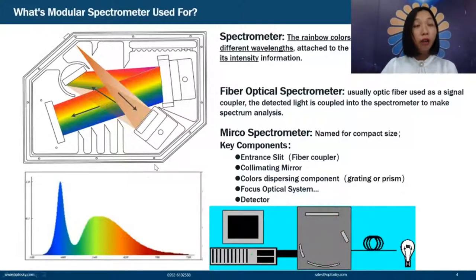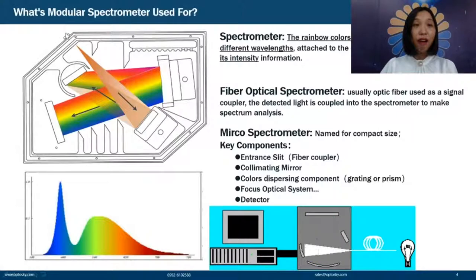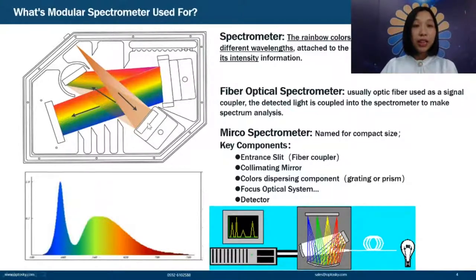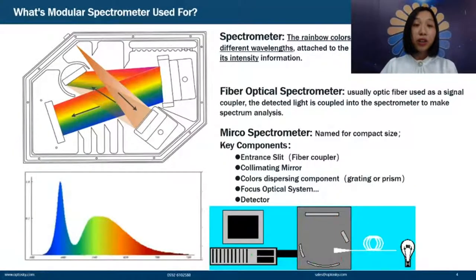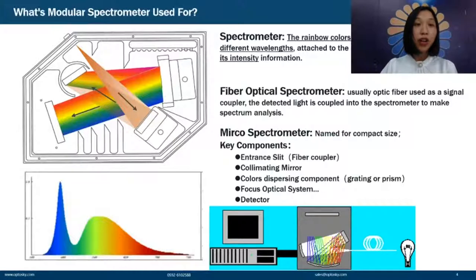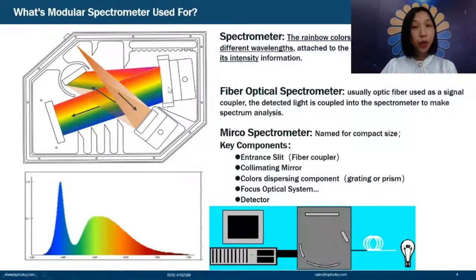What are the principles of a modular spectrometer? Light shoots in and passes through a slit, which forms a parallel beam. The grating then disperses the light. A focus mirror directs the dispersed light to the detector, which transforms the optical signals into electrical signals. This is the general working principle of a modular spectrometer.